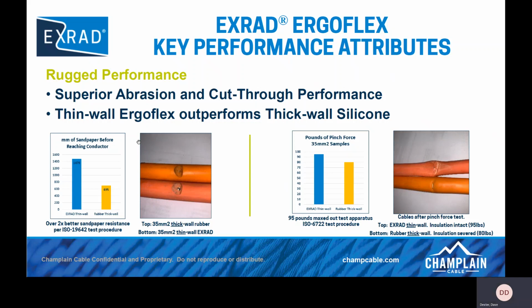Two performance tests are sandpaper abrasion and pinch resistance. On the left, you can see how thin wall Ergoflex performs over 2 times better in the sandpaper resistance test when compared to a thick wall rubber cable. And on the right, pinch force is also higher performing. In this test, Ergoflex achieved over 95 pounds of force, whereby the rubber thick wall cable was severed at 80 pounds. We should note that 95 pounds maxed out our test equipment, so we don't really know if actual failure would have occurred at 96 pounds, 106, or 116 or more.